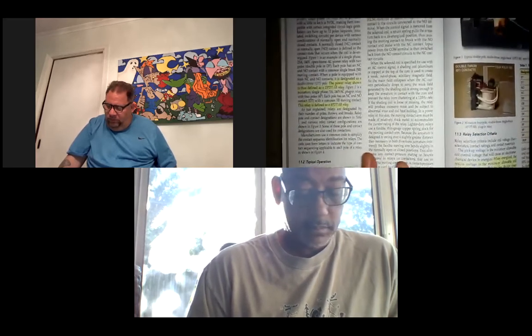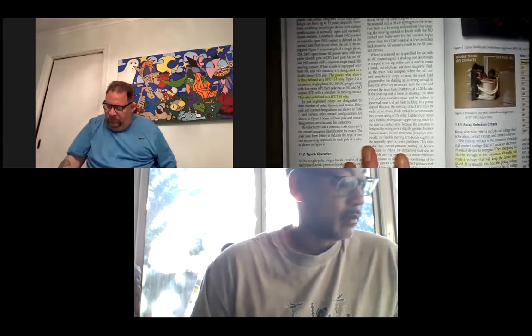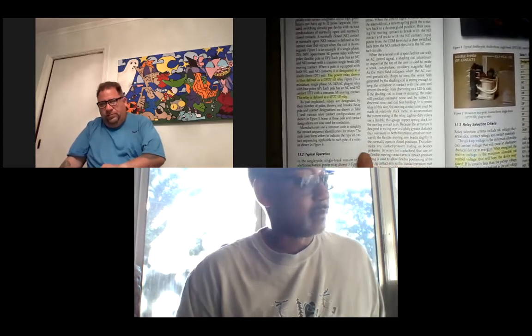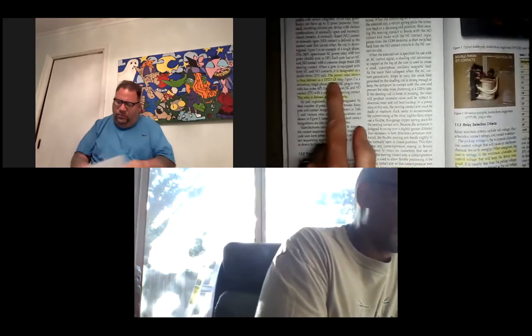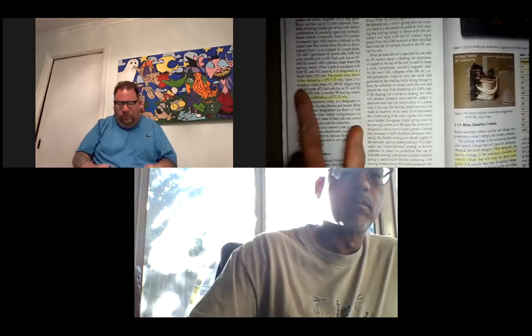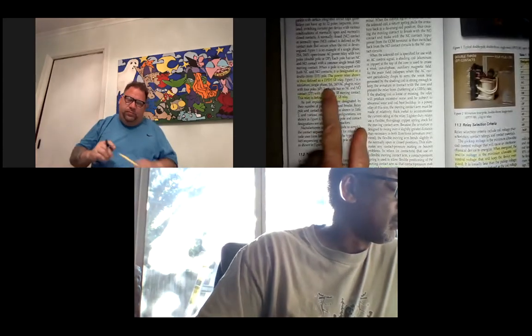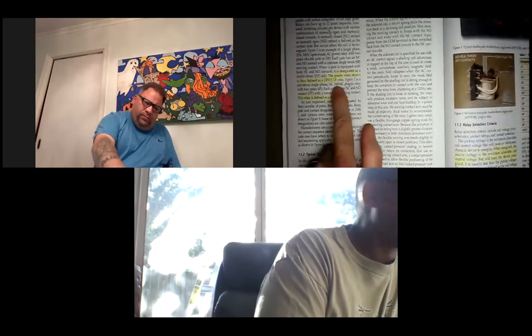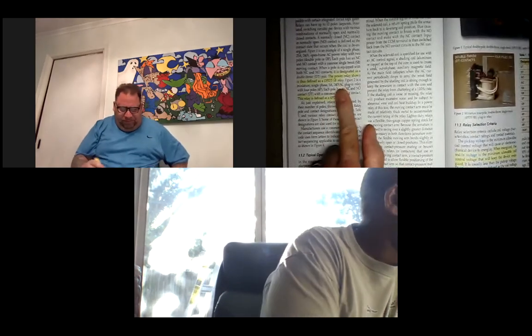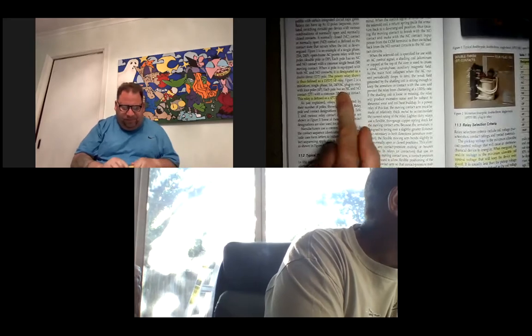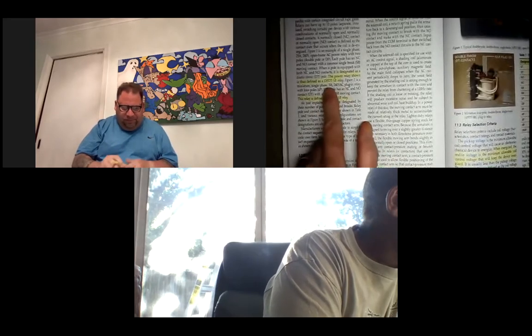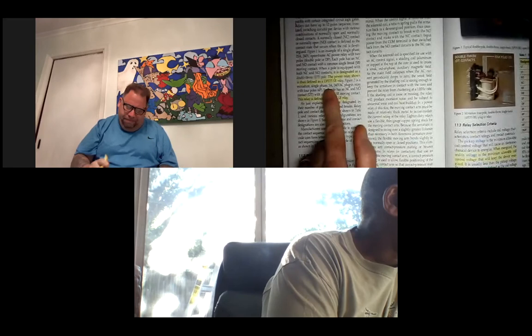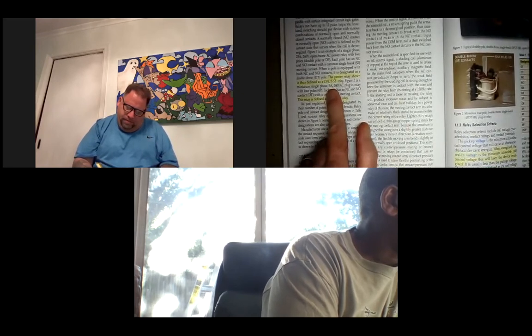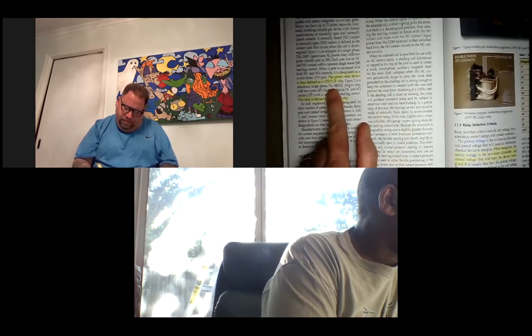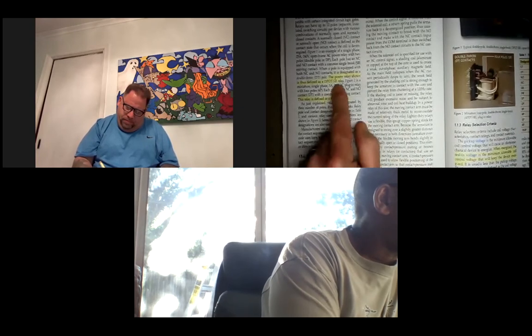Here on the left-hand side of page 2, just about halfway down the page, it starts. It says the power relay shown is thus defined as a double pole, double throw, single break relay. So double pole means there are 2 paths for current to go. Double throw means it has two positions that it can be in, almost like a 3-way switch.